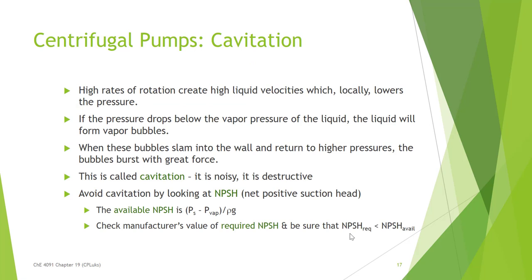Centrifugal pumps are great and we use them all the time, but they have a really serious problem: cavitation. When you have high rates of rotation, you get high liquid velocities, which can, at a single spot, immediately lower the pressure. If that pressure drops below the vapor pressure, it's going to form a vapor bubble. When that vapor bubble reaches a wall — the impeller vanes or the pump casing — it slams into it with great velocity and bursts with great force. This is incredibly noisy, destructive, and it's called cavitation.